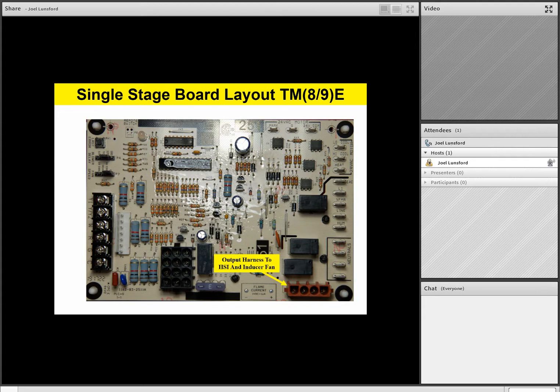Right next to that, we have a flame current pad. Now this is a really nice feature on our Champion furnaces. What this does is allow the technician to use a voltmeter to read his flame current. Now it used to be in the old days, so to speak, we used to have a special flame current meter. Well, you don't need that anymore with our Champion Johnson Controls furnaces because this flame current pad, if you will, is built right in on the control board.